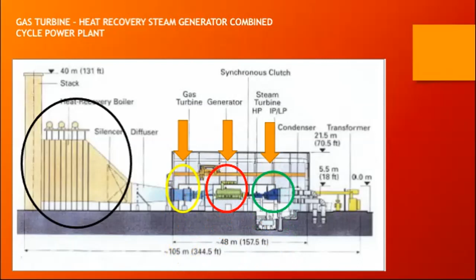Okay, here is an animation of the gas turbine during startup, until both the gas turbine and steam turbine are coupled to a common generator, and all these components are aligned, engaged, synchronized, and running at rated speed. Now, during startup, the generator acts as a motor, driven by a startup frequency converter, or SFC, for heat recovery steam generator purging for 10 minutes and to start up the gas turbine.